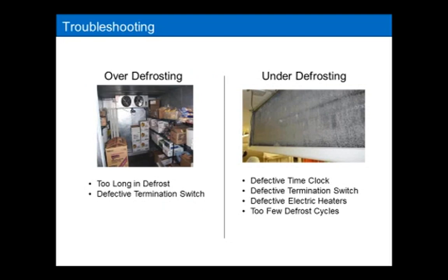You can easily identify under defrosting by an iced over frozen evaporator.